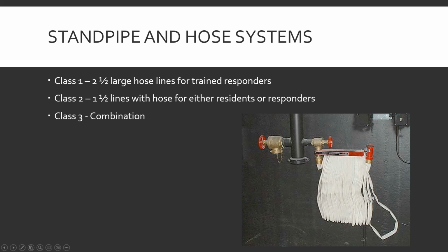Now, a point on standpipes. Well, not standpipes, but the hose systems. Don't use these. One of the first things you'll learn in an official class, or I'm telling you now as a heads up, these don't get tested ever. The building is built, they connect the little single jacket forestry-like line, the little plastic nozzle, and go there. Cool. And then it never gets touched ever. So these will break or this will dry rot. If you want to use the 1.5 or 1.75, disconnect it, use your own hose, problem solved. Less headache.